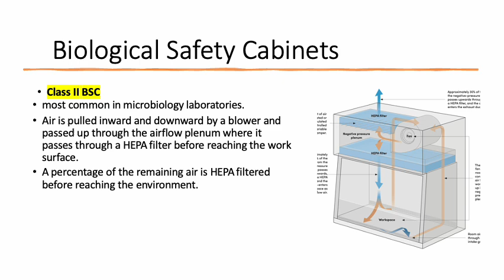So, usually po, biosafety class 2 po has two sets of HEPA filter. So, yung isang HEPA filter po will filter the supplied air inside the cabinet and another filter po should filter naman yung air that will go outside the biosafety cabinet, providing complete protection. It provides personal protection, environment protection, and also sample protection, okay, or product protection.